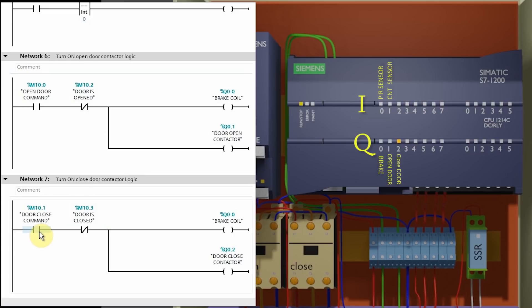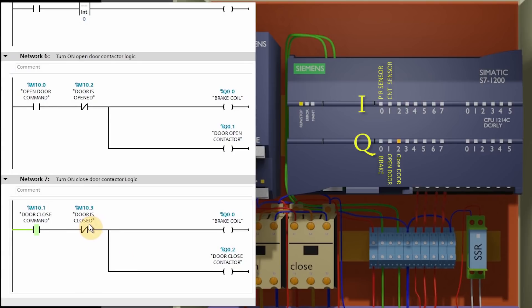Network 7 is to turn on the brake coil and the door close contactor to run the motor in the reverse direction. Once M10.1 close door command bit is on, it will turn on the brake coil and the close contactor. The brake coil and door close contactor will stay off if the door is already in the closed position, because M10.3 normally closed contact is used in series with the output bits — M10.3 will open if the door is already in the closed position, keeping the brake coil and motor contactor off.